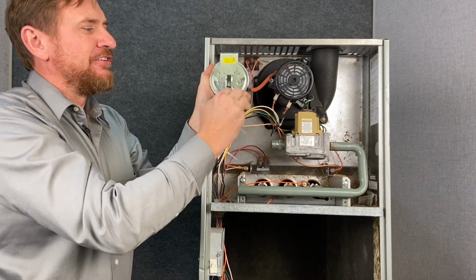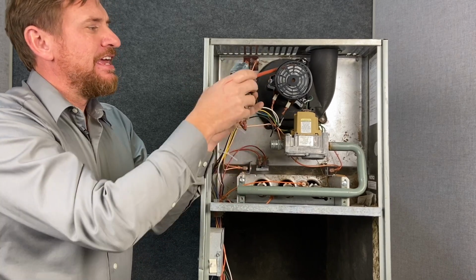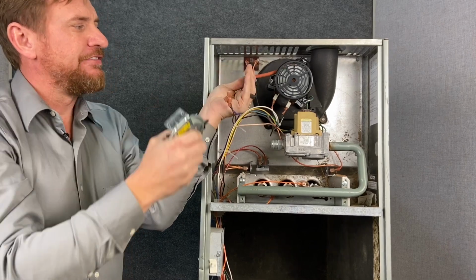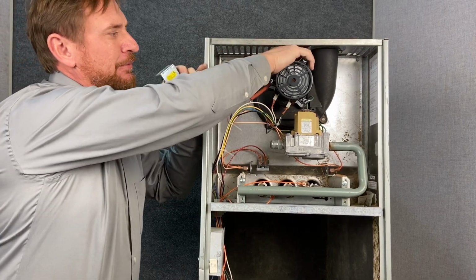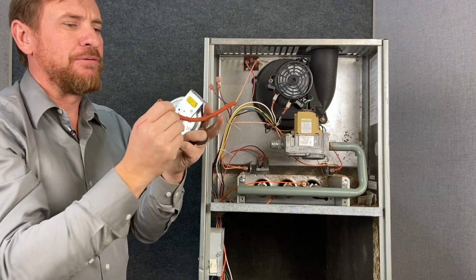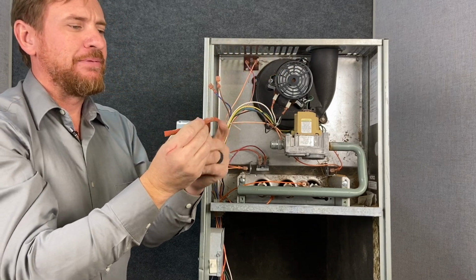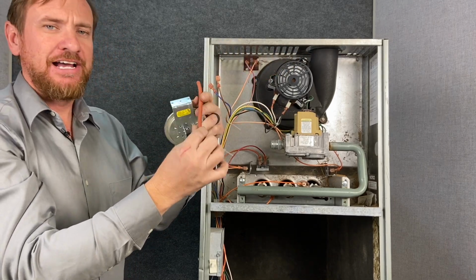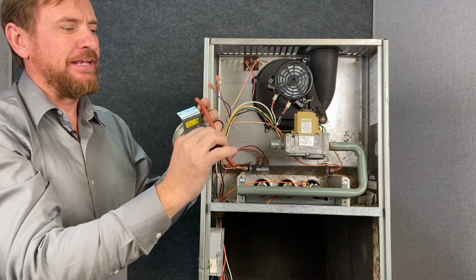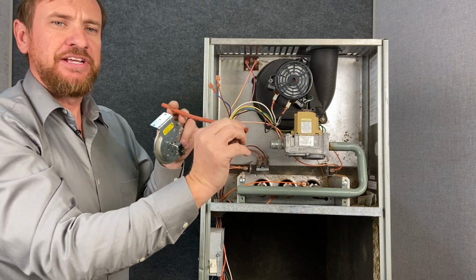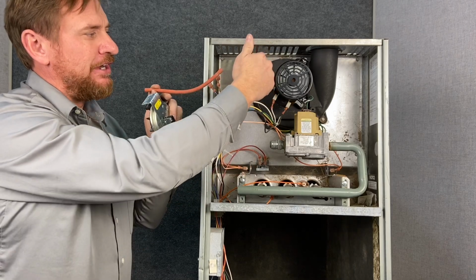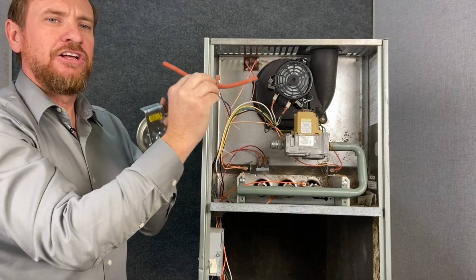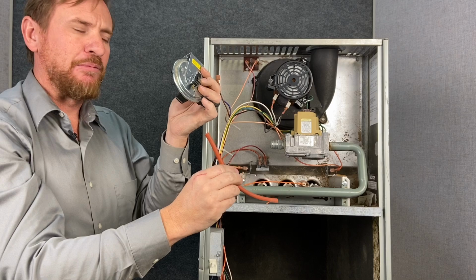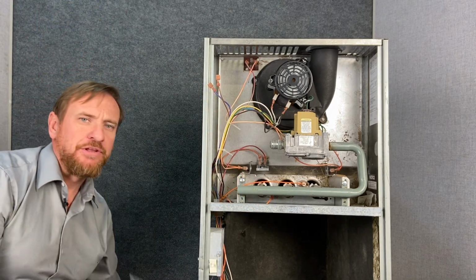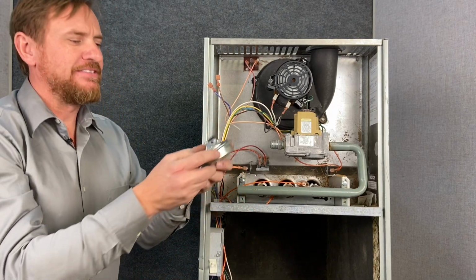We're going to take this loose, and we're going to take this loose. And what we're going to do is just pull this little hose off. Now this hose we need to be very careful with. I'm going to pull it off with the inducer motor completely, but this hose ends up getting cracked and dry rotted over time. This is going to be one of the things that you have to replace. So these hoses can also get stopped up. You can get bugs or other buildup in there, and it can clog this hose up, and it won't pull a vacuum to our pressure switch. Also, we're going to take one of these pressure switches apart so we can see what's inside.